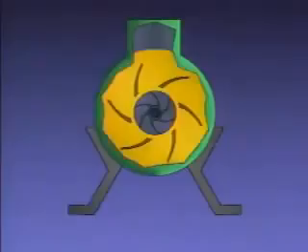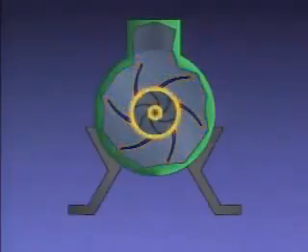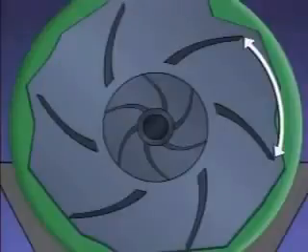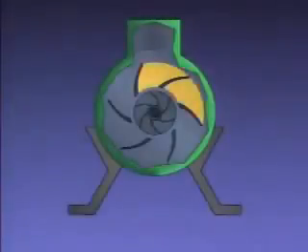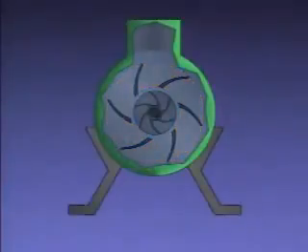A diffuser consists of a series of stationary vanes that surround the impeller. The distance between the outer tips of the vanes is greater than the distance between the inner tips. As a result, the vanes create a series of small volutes all around the impeller. This arrangement of vanes balances the radial thrust around the impeller.